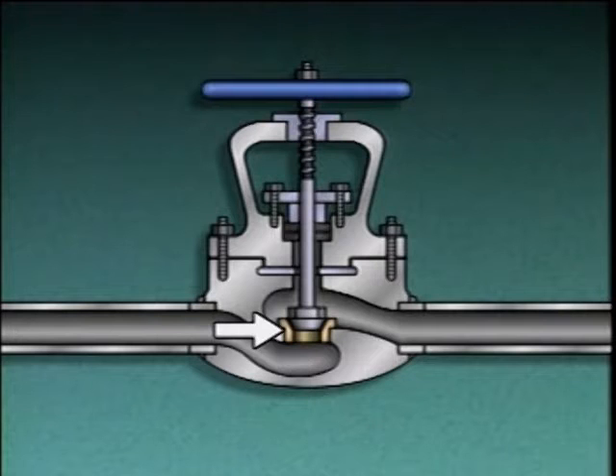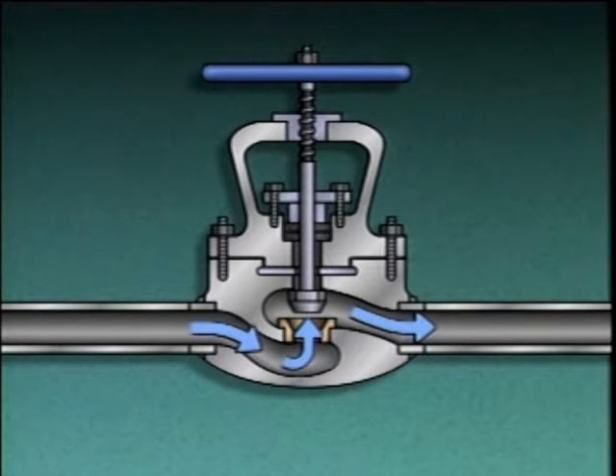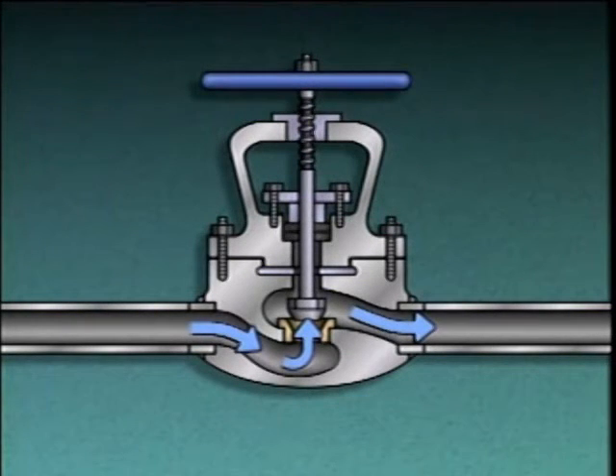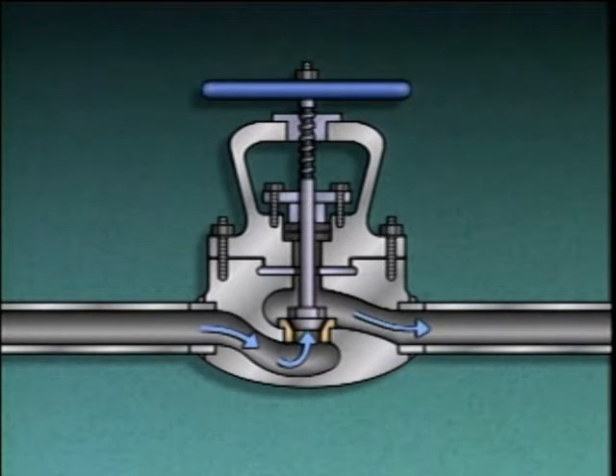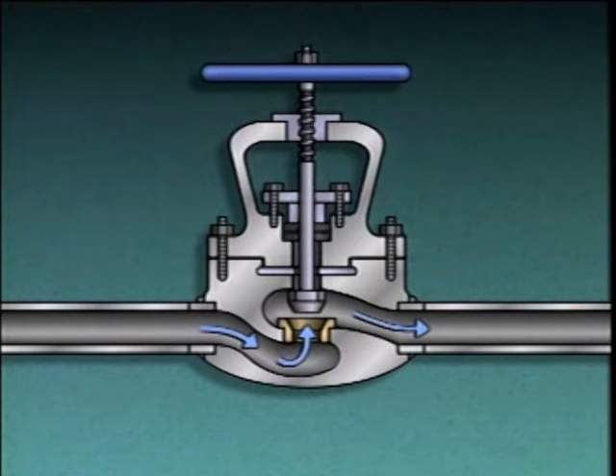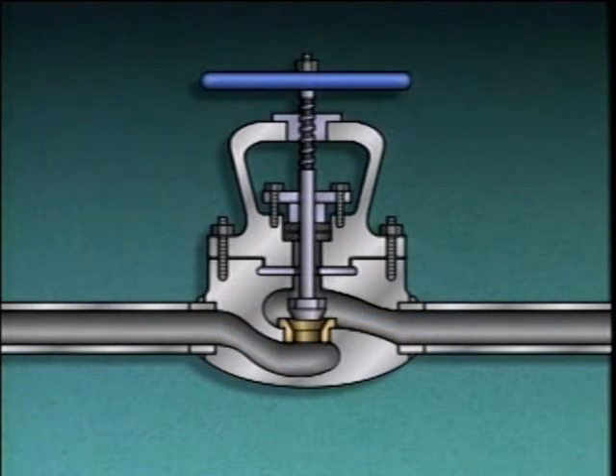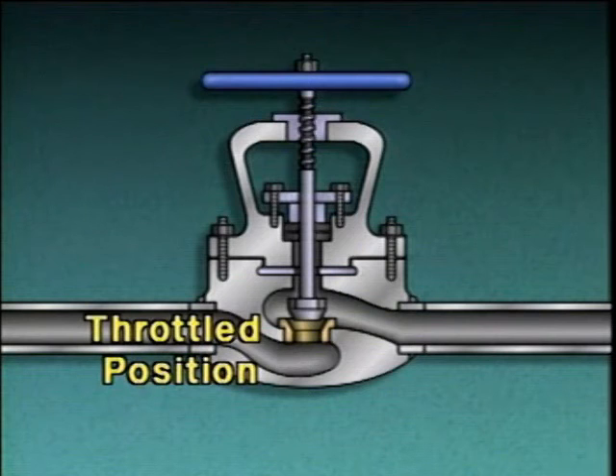The seating area or seat is a stationary part of a valve. It's used with the disc, which is a movable part, to control flow through the valve. As the disc moves toward the seat, flow through the valve is reduced, and when the disc presses against the seat, flow is stopped. As the disc moves away from the seat, flow increases until the disc reaches its limit of travel — at this point the valve is fully open. When a valve is partially open, it is said to be in a throttled position.